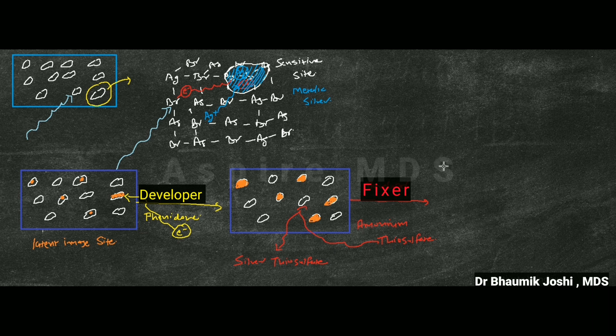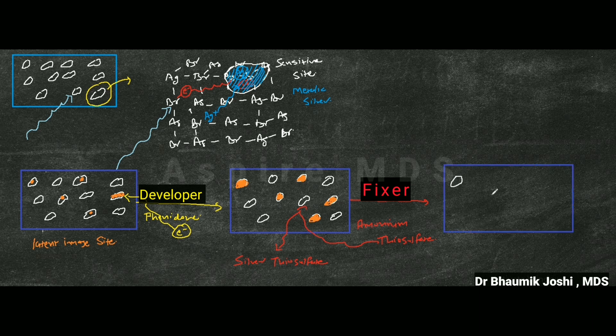This silver thiosulphate, when you wash the film, will be drained out of the film surface. After the fixing process is done and the film is washed, all the silver thiosulphate is washed out, and the only structures remaining on the x-ray film will be where latent image formation had taken place.